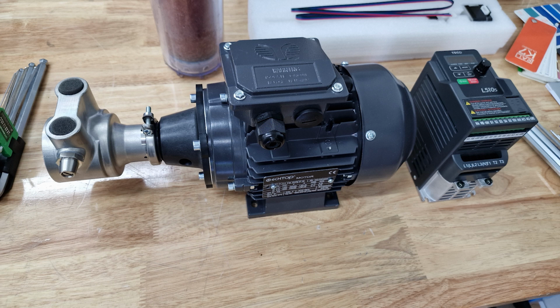Then there's the centrifugal vane pump, whose motor cools itself with a fan blade on the motor axis that sucks in air, but only if the motor RPM is above a certain level. In the EDM application, the pressure is really high but the flow is really low, and the motor RPM is quite low while the pressure is high, so the motor has to deliver a fair amount of power at a low RPM.